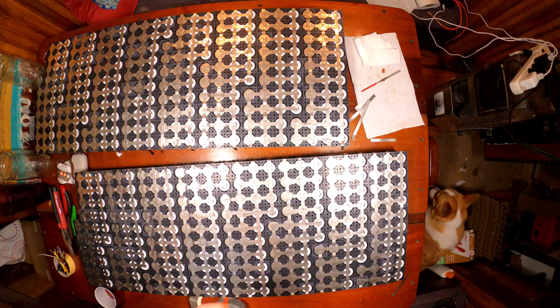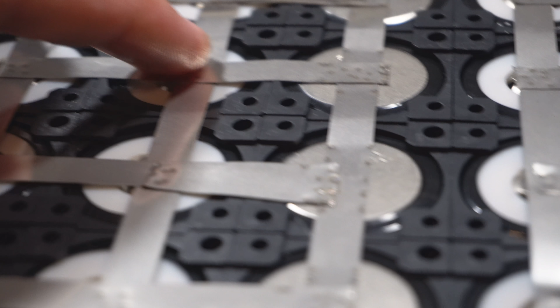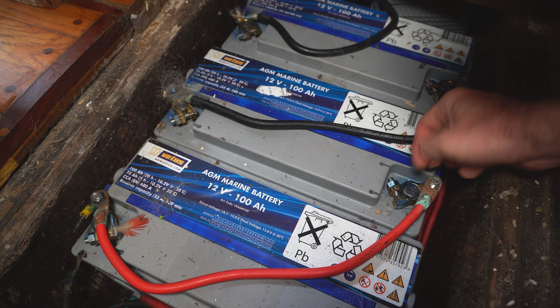So what do you do when you have 10 interconnections available, which would only give you the ability to flow 50 amps, but you want to flow 80 amps like in our case? It's simple, you add more. We make sure we have 16 interconnections between every single one. This is one interconnection, and when there's not enough space, you stack 2, and now you can flow 5 and 10 amps. This little bridge flows 10 amps, where this one right here only flows 5. It's simple math. Together, with all these extra ones, it adds up to 16 strips interconnecting the battery bank, giving us the 80 amps we need. That way everything works just fine. It's all about planning what you need and then factoring in safety factor on top of safety factor.